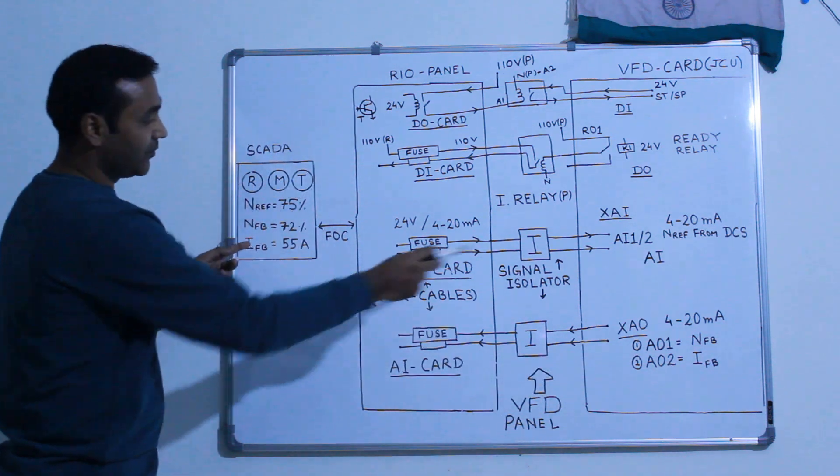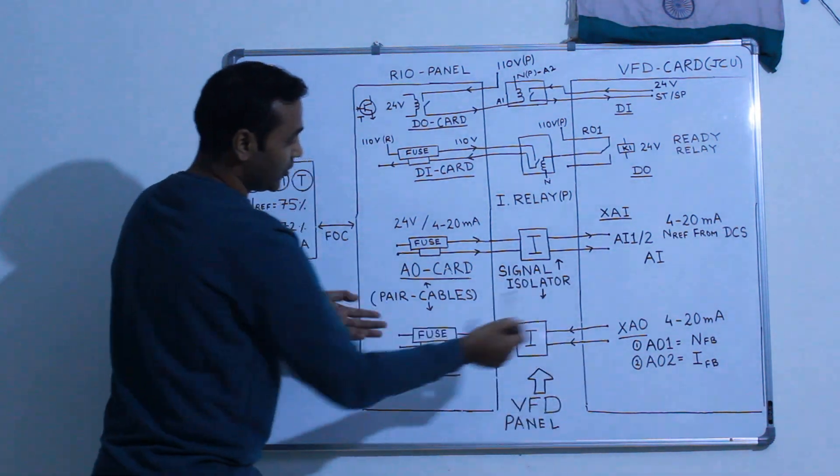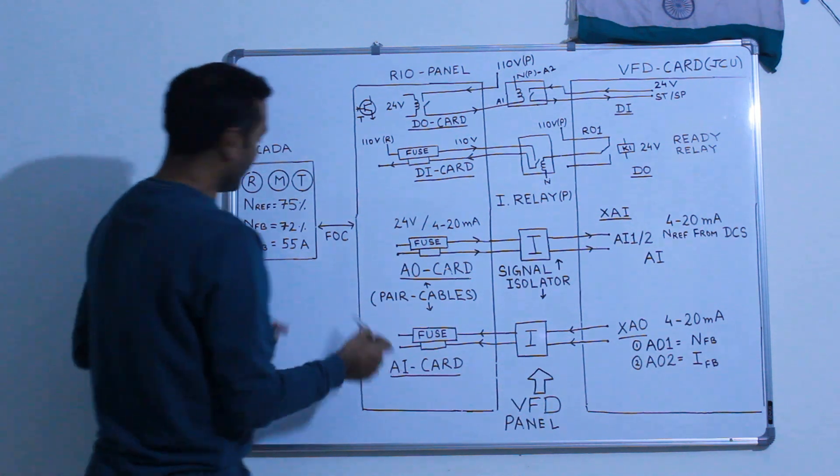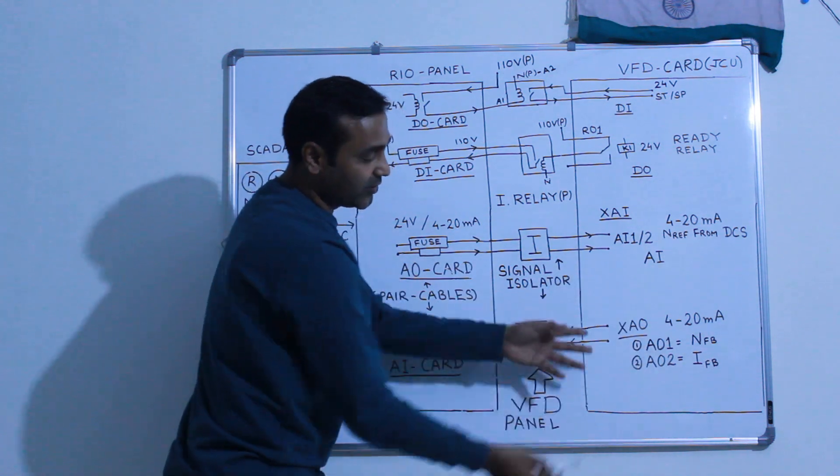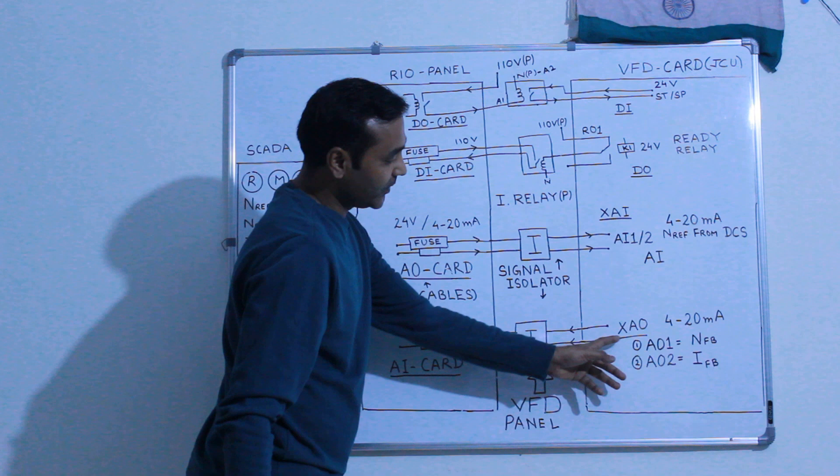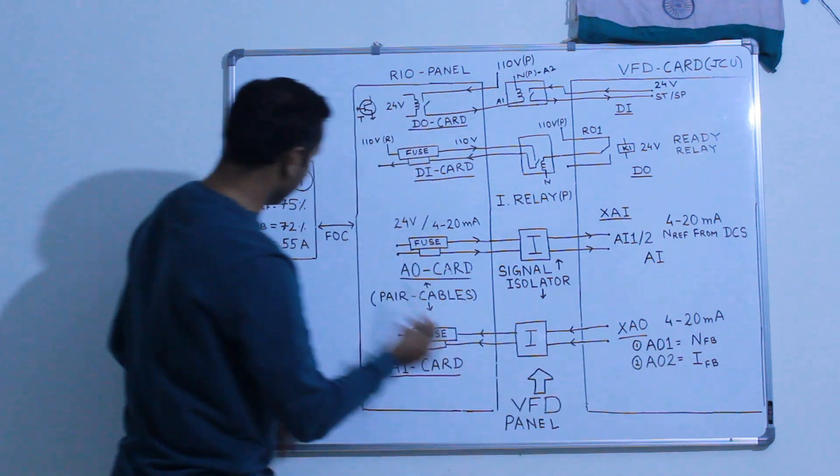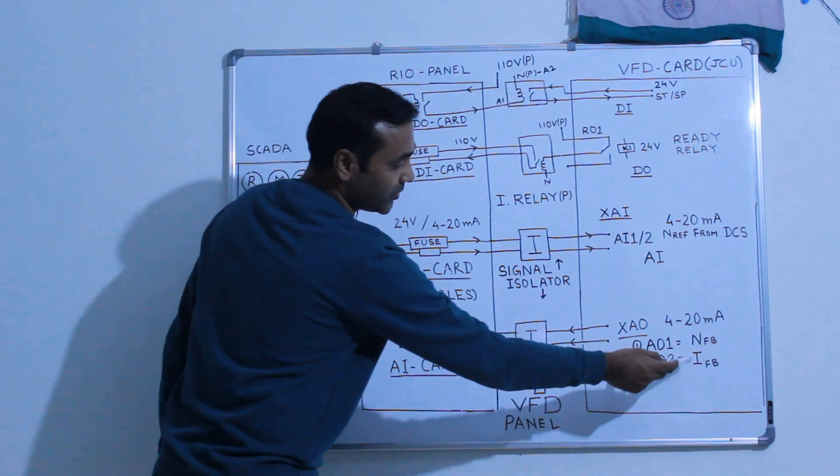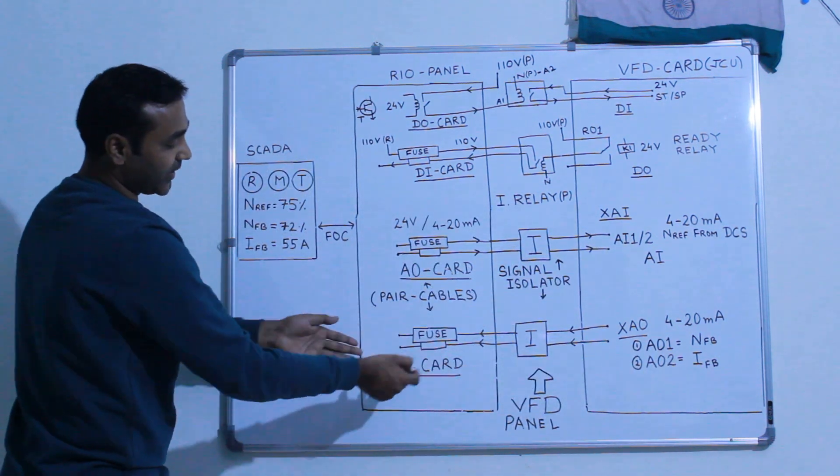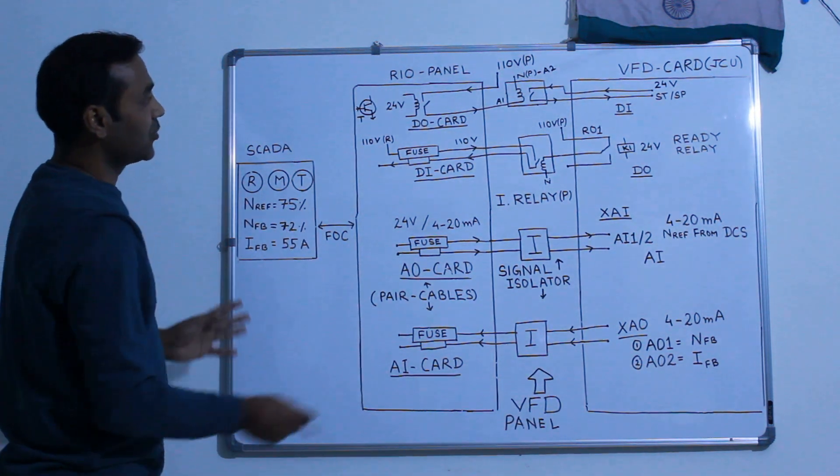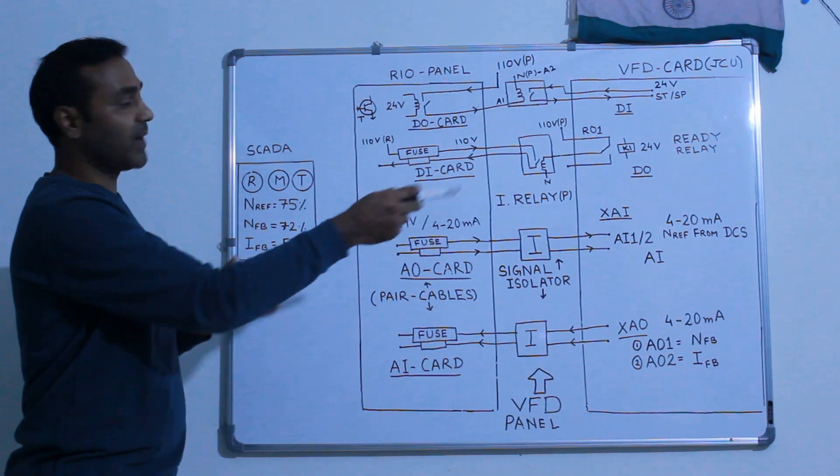Now since the drive is running, the drive has to give feedback that will come back to SCADA, from VFD to RIO and RIO to SCADA. First one is 72 percent speed feedback. Similarly like how it was generating, the card will also generate internally. There will be two different slots - analog output 1 for speed feedback 72 percent, and analog output 2 for current feedback. Similarly it will flow back, it will get here, and from this card it will come back to the SCADA. That's how all these four signals flow between RIO panel to card and to SCADA back and forth.